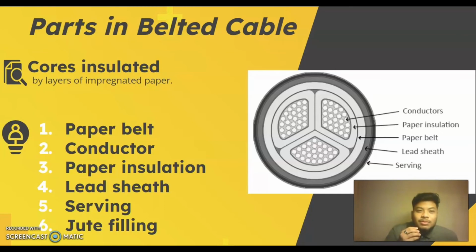So I'm going to present about parts in belted cable. So the first one is the core insulated by impregnated paper. And for the parts in belted cable, there are 6 parts: number 1 is paper belt, second is conductor, third is paper insulation, next is lead sheath, number 5 is serving, and the last one is jute filling.